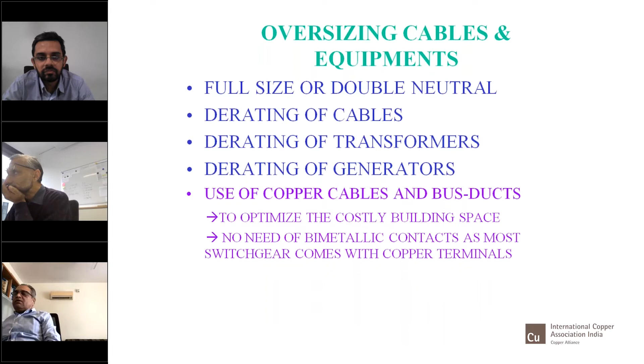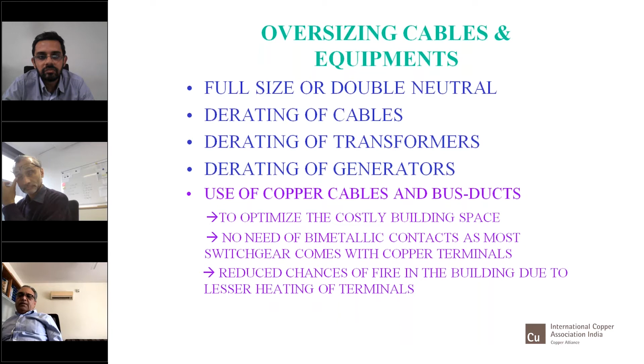And then if you use copper, again, there is no need of bimetallic contacts, because most of the breakers, MCCBs or MCBs or ACBs, they all come with copper contacts. And so when you connect to an aluminum bus bar, you need to use bimetallic contacts. No need. You just use the copper. It reduces chances of fire in the building due to lesser heating at terminals, which I had spoken to you about earlier.